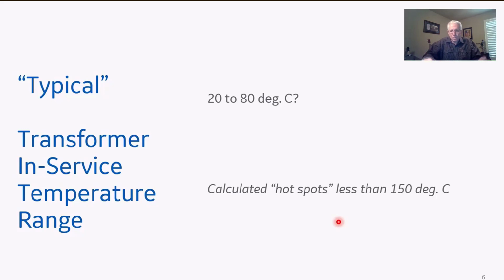That's the $64 question. When thermal is developing but the paper's okay, I'd say a good 9 out of 10 times you're probably going to be able to repair that. Now, there are instances I've seen where leads were buried up underneath the winding, and those connection points couldn't be accessed - there was no way to reach those connections that were overheating.